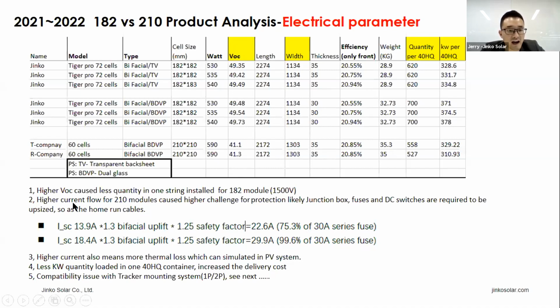Higher current means you need stronger and safer protections for equipment like junction boxes, fuses, and DC switches, as well as the home run cables. The home run cables connect the strings between the strings and the combiner box.